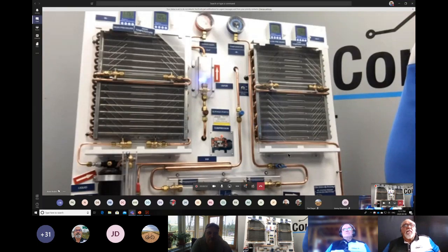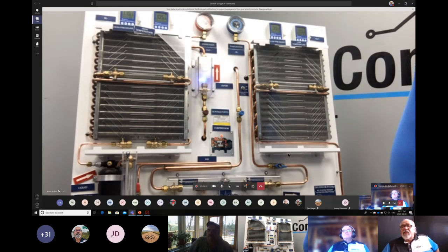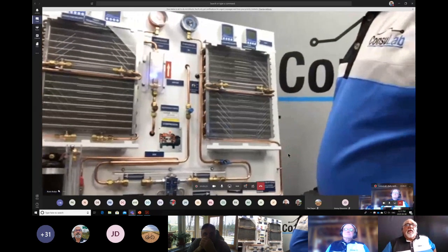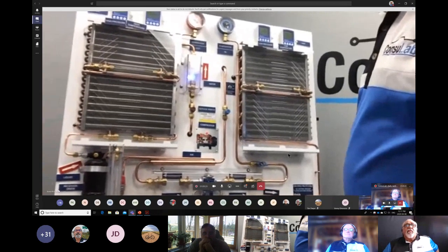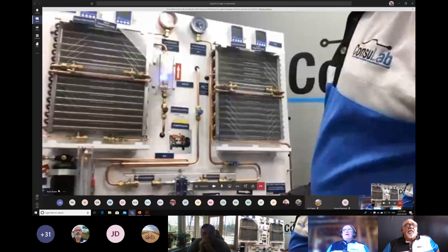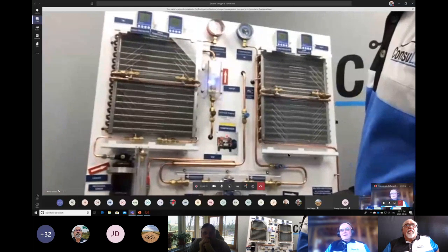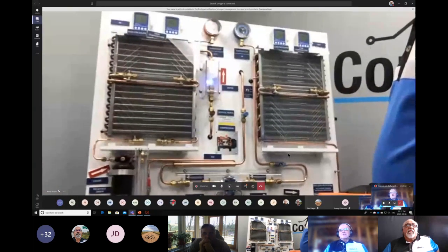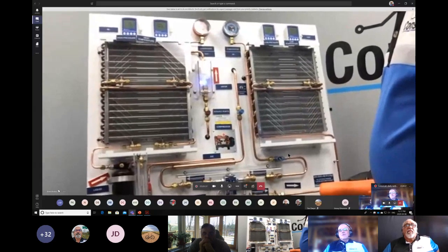What if it was 15 degrees of superheat? There could be the possibility that that's where it's set, or another indication is that if it's not within its set limits, we usually say that a TXV should be in that 8 to 12 degrees of superheat, it's usually an indication of a low liquid level in the evaporator, meaning that we're adding too much heat, we're getting too much vapor, and we're getting lots of superheat. And just one point, I want to add that the superheat for a TXV is different than the superheat for an orifice tube.